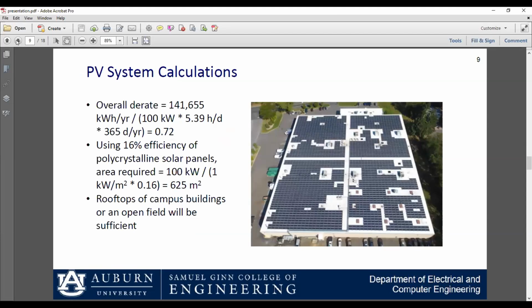For the PV system calculations, using that annual production of 141,655 kilowatt hours, 100 kilowatt system size, 5.39 hours per day, and then 365 days. It's a 0.72 derate. And then we used the standard 16% efficiency for a polycrystalline solar panel. And then the area required was 625 square meters. On a college campus, this required area can be met with available space on campus building rooftops, or even an open field.